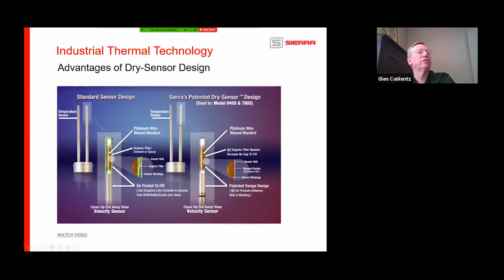Okay, looking more closely at the dry sensor design, everybody else's sensor that's out there has an organic between the RTD and the stainless steel sheath. And if you're constantly heating and cooling this, you're creating gaps, air pockets, and that is causing drift in a thermal mass flow meter. Everybody has it. But if you look at a Sierra design in a Quadratherm, and also the same sensor is used in the 640S and the 780S, there's no organics in here, so there's nothing to break down. So in theory, it should not drift. And over the last 10 years, actually more than that, because being introduced in this 640S and 780S, it does not drift over time. And we back it up with a lifetime warranty on the sensor.